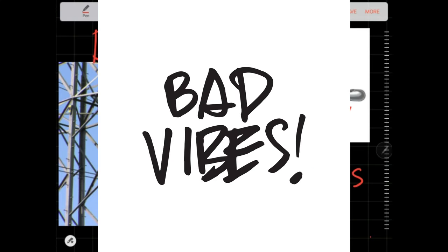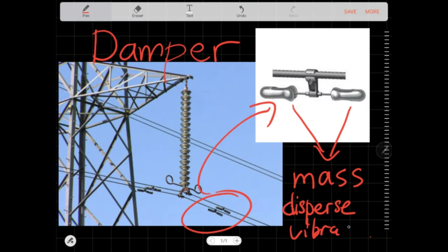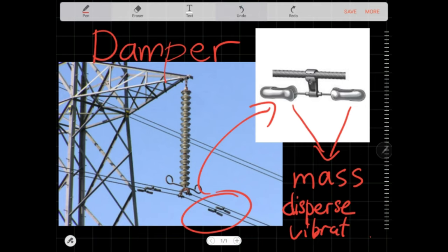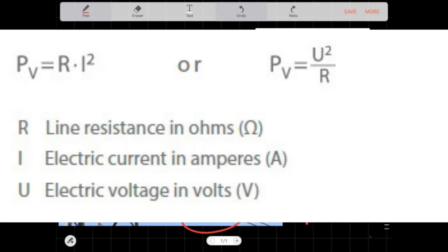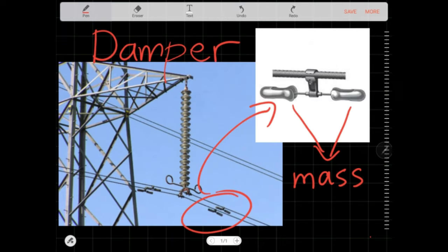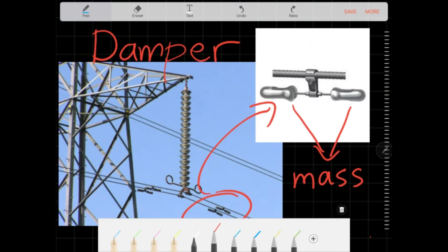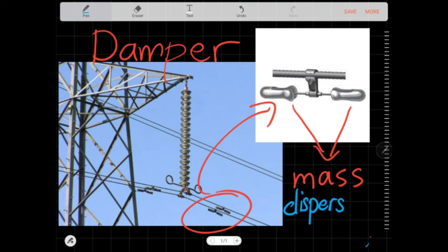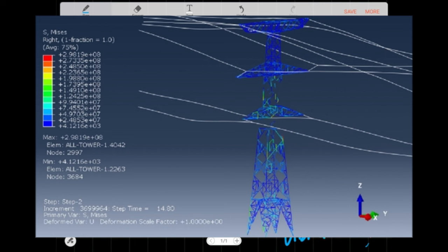So, is the vibration bad? Vibrations can cause the conductor fibers to rub against each other or against the insulator joints, which can increase the resistance of the transmission line and cause power losses. That is not good. It can also cause the conductor strands to wear out. And if it breaks or snaps, not only will you lose the line, but the transmission tower also relies on the tension to balance out the forces. So, the tower may actually collapse if the forces are not balanced out properly.